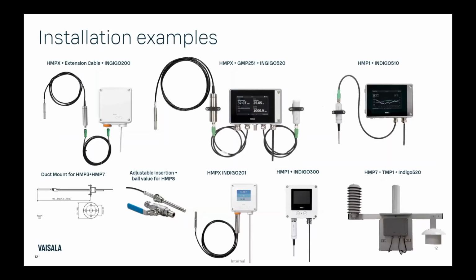So here are a few installation examples. Over on the left, we have the HMP3 probe with the Indigo 200 non-display model. You'll see there's a remote probe cable in between the transmitter and probe. That's just a female to male adapter if you need some extra probe length. You'll also see in the bottom middle of this diagram, you can also connect that probe body directly to this locking wheel if you wanted more of a fixed design without that intermediate probe.